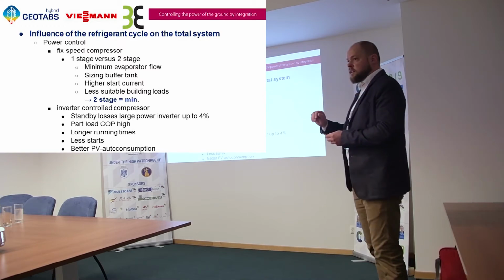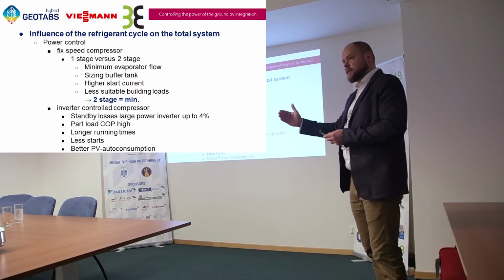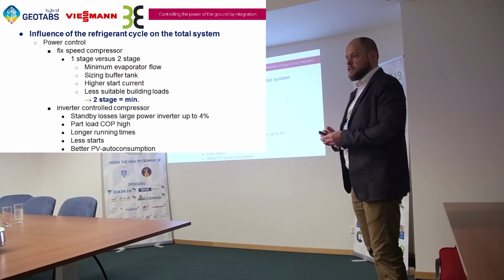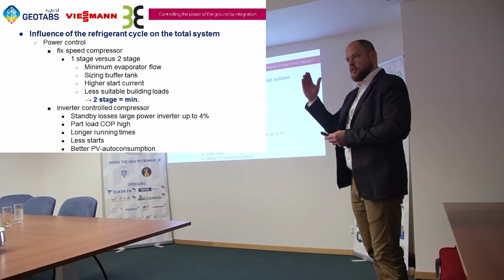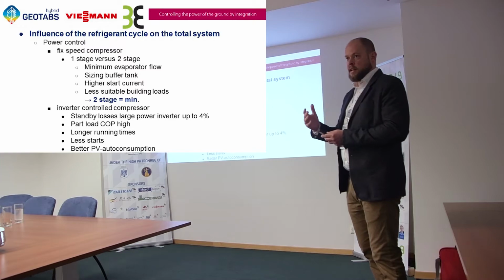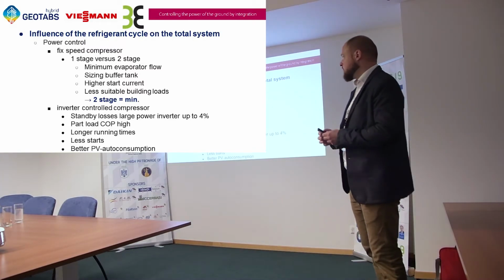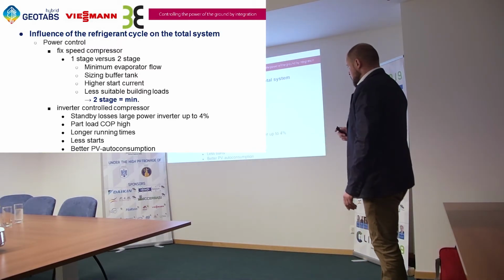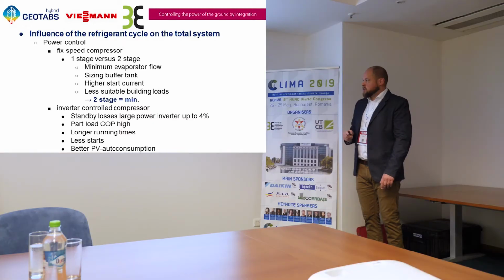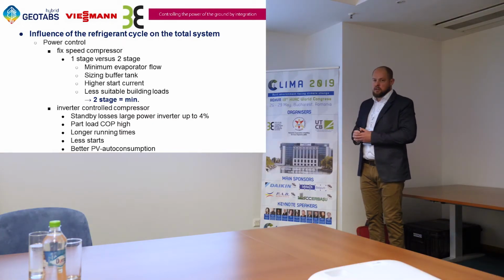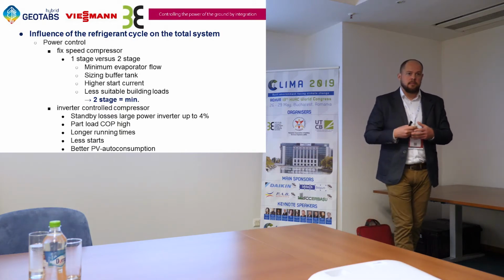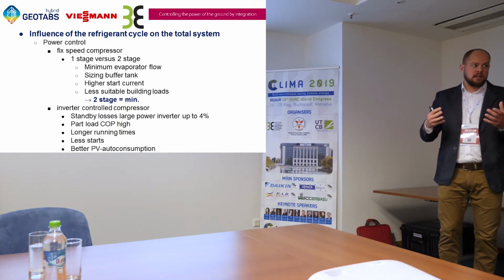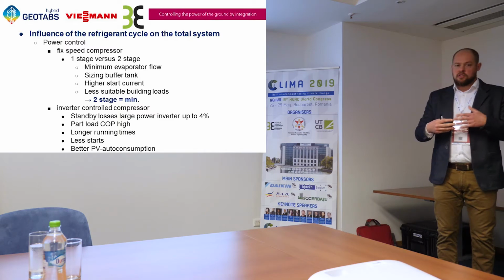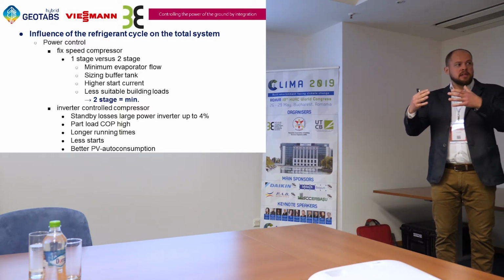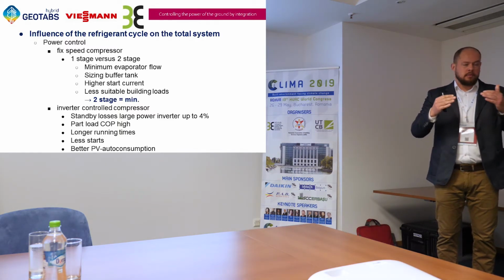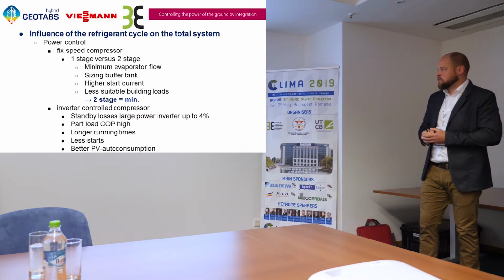And why do we do that? That is to have a minimum running time of the compressor. It's very important that the compressor is not switched on-off, because it will wear the compressor down much faster. Also mind that when you use a one-stage compressor, you have a much higher start current. In Belgium, for example, a building or a company is charged on these peak currents they use. So when we can keep the peak currents low, it's better for the energy bill.